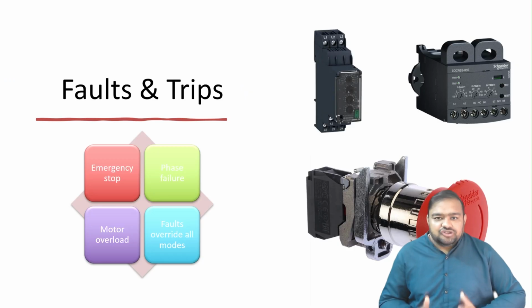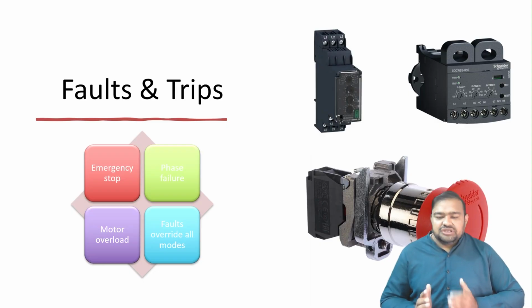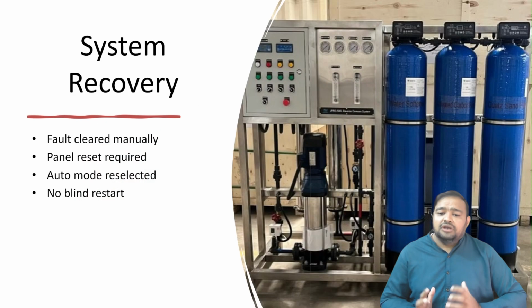Certain faults must stop the system immediately: emergency stop activation, phase failure, or overload trip. These faults override auto and manual modes, require operator reset, and are typically latched using control relays. After a fault is cleared, the panel must be reset, auto mode must be reselected, and the system resumes normal operation. Automatic restart without operator awareness is never recommended in industrial systems.